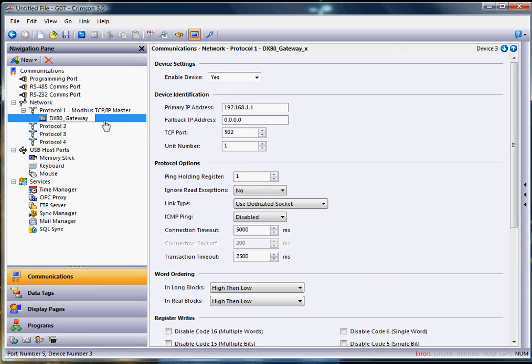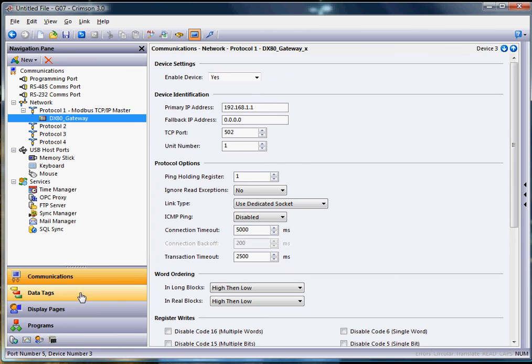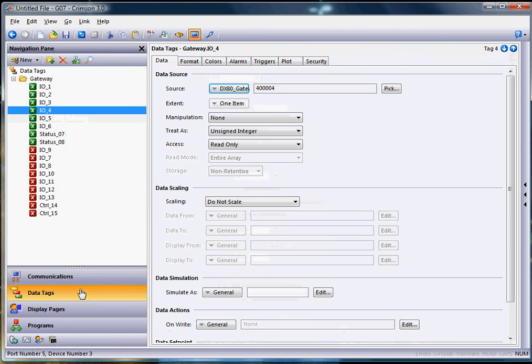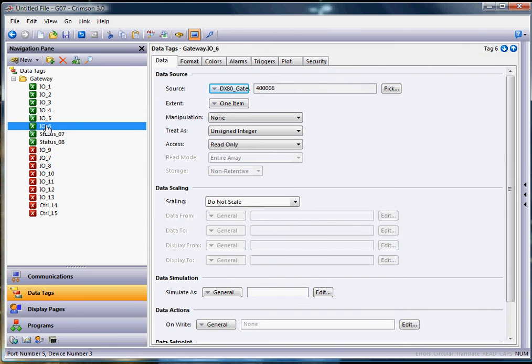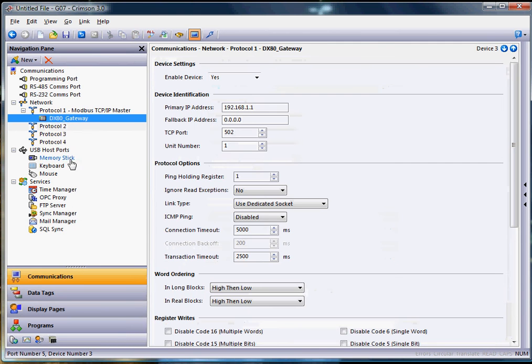And then when you hit enter, watch what happens. You see the little errors down here. Watch what happens when I hit enter. Here we go. Boom. You can see that the errors down below here got cleared up. And if I go back to data tags on the left, all of a sudden all these tags are now relinked back to that same device. However, it is now talking to it over the ethernet port versus the 485 port.